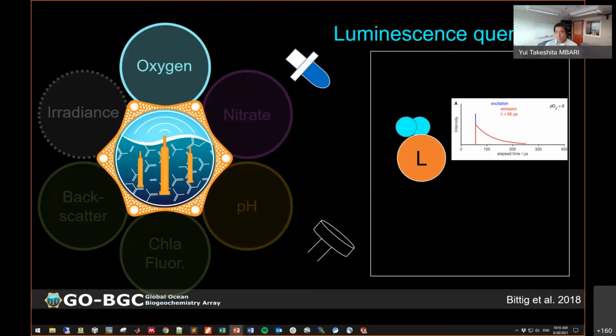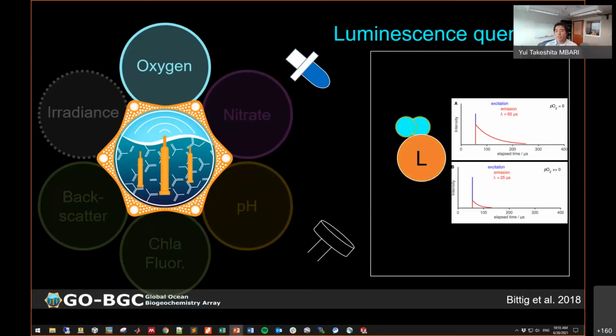But if there's oxygen present, shown in the blue here, then the luminophore can transfer some of its energy to oxygen molecules directly without luminescing. Therefore, it reduces the decay time. We measure this difference using a phase shift. That's the analog signal, and then we use the Stern-Volmer equation to calculate oxygen concentrations. Again, all the details for this are in the pre-recorded talks.